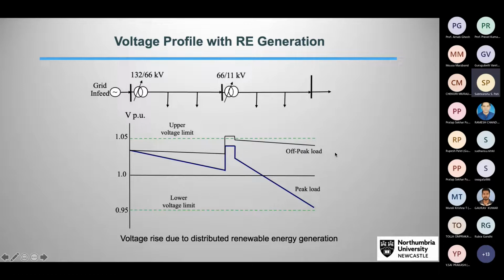And during off-peak, when we have minimum demand on the grid, obviously current is lower and voltage drops are lower, and therefore the voltage is higher at each point on the loads here. At peak demands, we have more voltage drop.